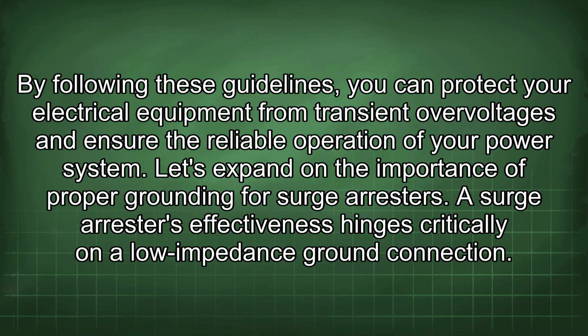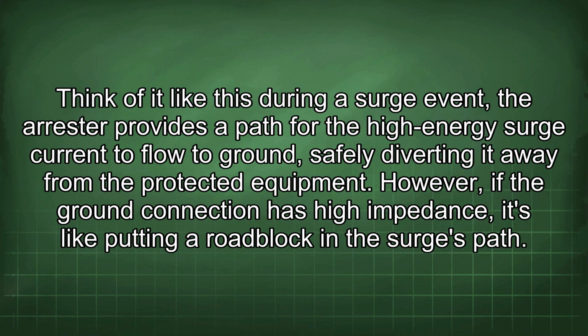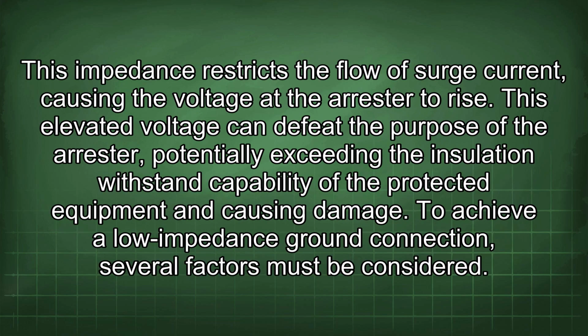A surge arrestor's effectiveness hinges critically on a low-impedance ground connection. Think of it like this: during a surge event, the arrestor provides a path for the high-energy surge current to flow to ground, safely diverting it away from the protected equipment. However, if the ground connection has high impedance, it's like putting a roadblock in the surge's path. This impedance restricts the flow of surge current, causing the voltage at the arrestor to rise. This elevated voltage can defeat the purpose of the arrestor, potentially exceeding the insulation withstand capability of the protected equipment and causing damage. To achieve a low impedance ground connection, several factors must be considered.